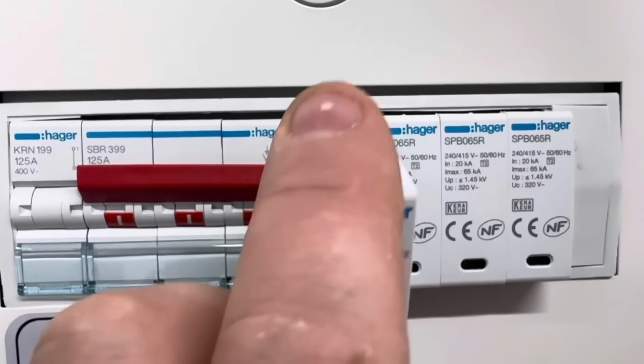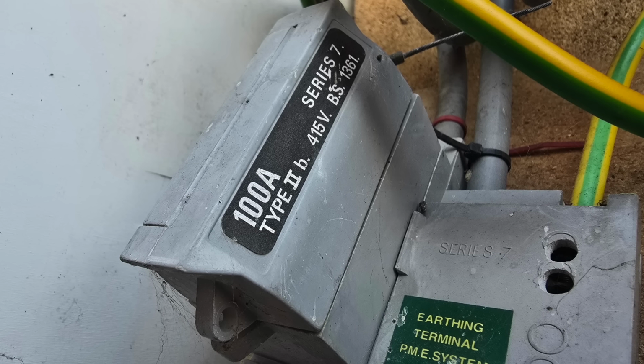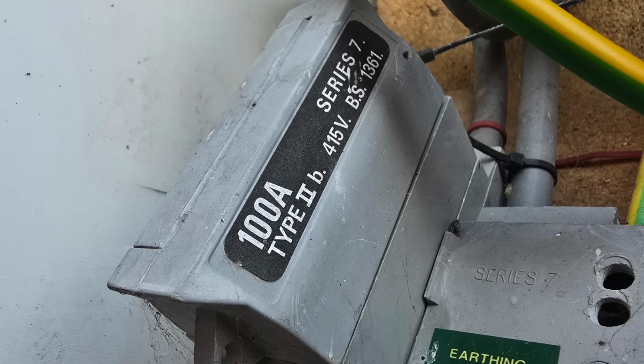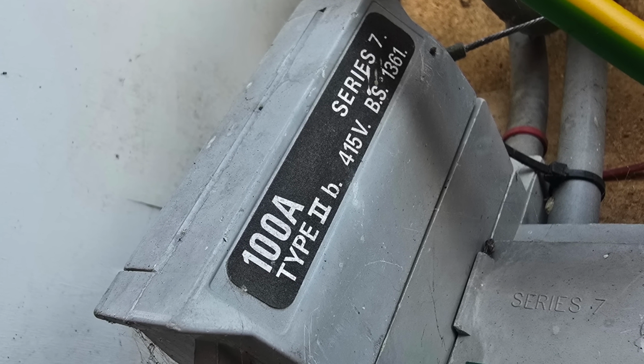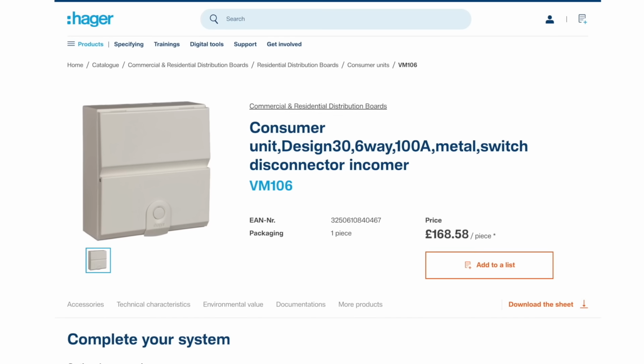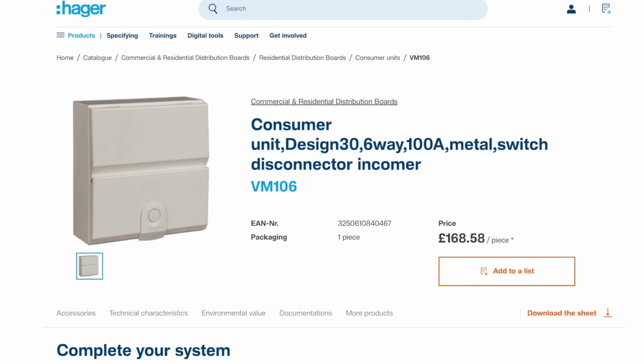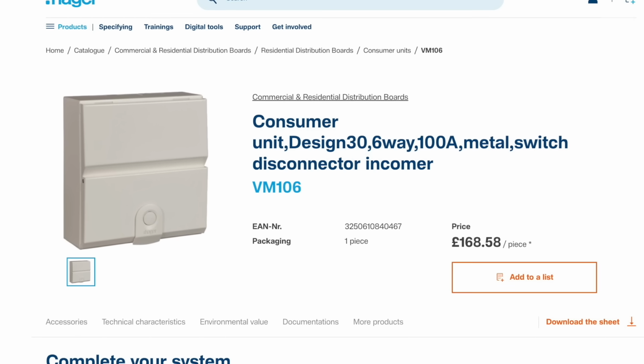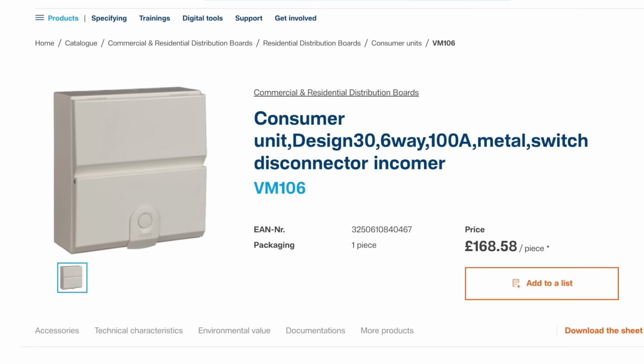However, big brands such as Hager say that the service cutout fuse plays a critical role in providing protection to the assembly arrangement. The company says that consumer units complying with the standard BS EN 61439-3 have a conditional short circuit rating of 16 kA. This means they're designed to withstand fault currents up to 16 kA when installed with a suitable upstream protective device such as the supplier's cutout fuse. This rating is conditional because the consumer unit and protective devices alone cannot clear such high currents.